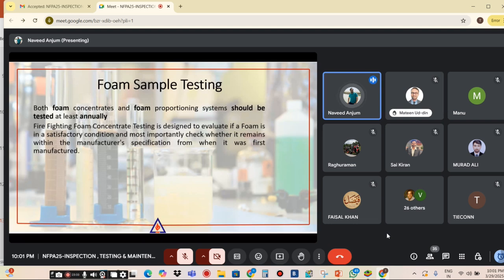Secondly, we also have to check our foam system, like the foam chambers in our fire tanks, and the bladder tank and any other type of tank. So we have to check them, but it is not required to check them with foam.